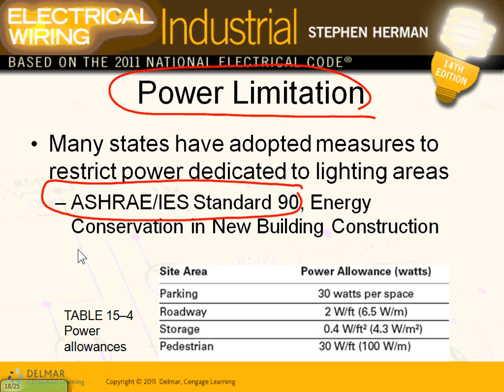In a parking lot, they give you 30 watts per parking space. ComCheck does all this — all you have to do in ComCheck is get the square footage of the parking lot, the type of fixture, and the wattage. ComCheck will do the calculation for you based on these criteria. If you have roadways, storage areas, or pedestrian areas, it gives you different values per 1,000 square meters.